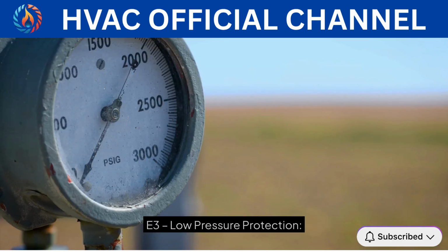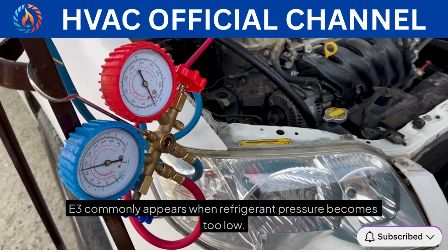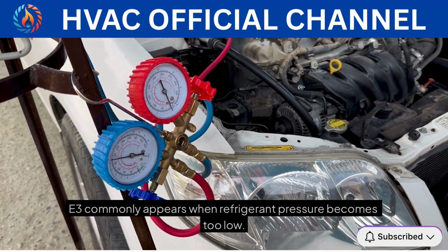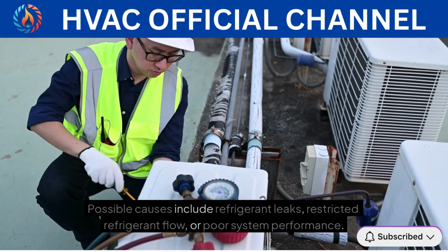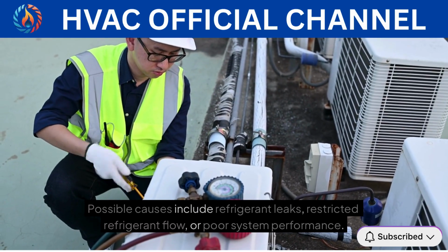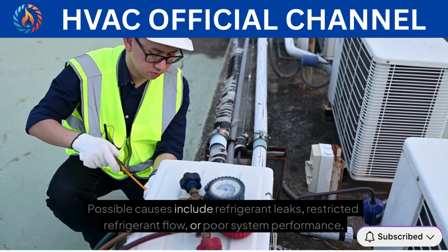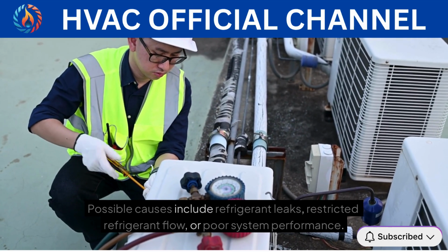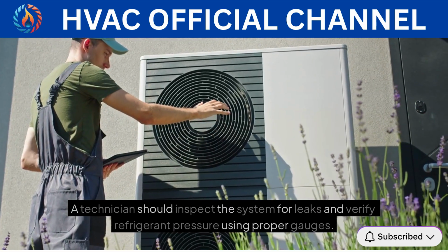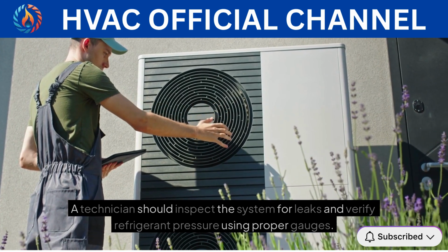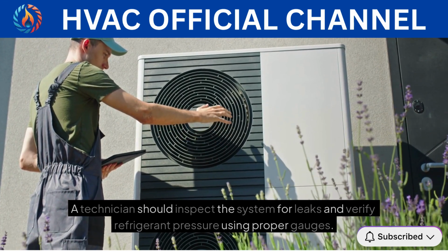Error code 3, E3, low pressure protection. E3 commonly appears when refrigerant pressure becomes too low. Possible causes include refrigerant leaks, restricted refrigerant flow, or poor system performance. A technician should inspect the system for leaks and verify refrigerant pressure using proper gauges.